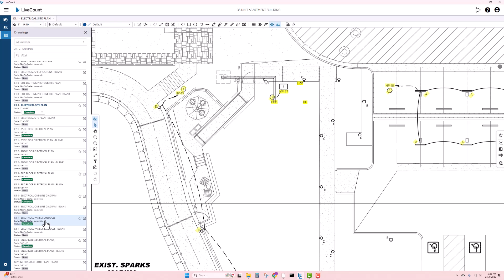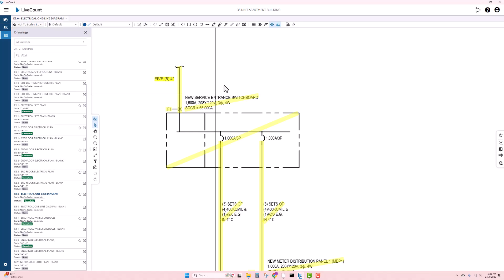Okay, as far as feeders go, you're gonna go to the one line diagram, which I have pulled up here. So, one line diagram. This one, we've got 5 4-inch going in. As you can see, they didn't show on the drawings what they were actually including, so I referenced the utility drawings. In this case, we had 5 4-inch. So you have 5 4-inch coming from the transformer into the service entrance. And these are gonna be empty conduits. The power company is responsible for providing the cable, pulling the cable, and making all the terminations.